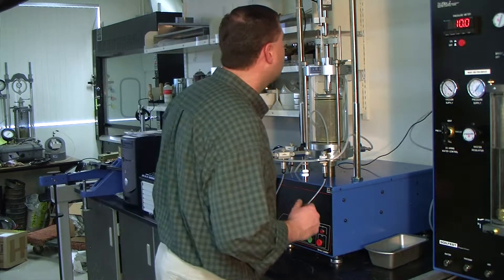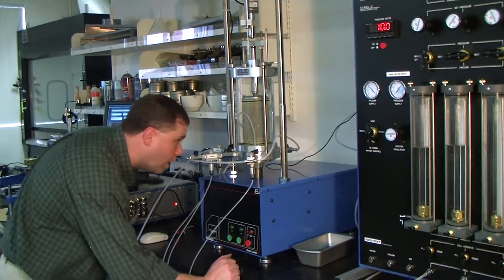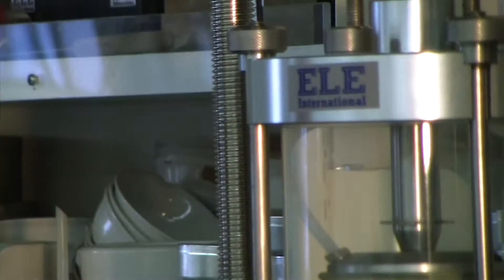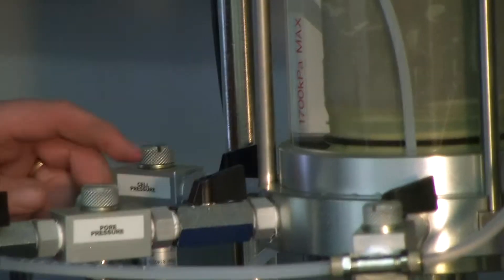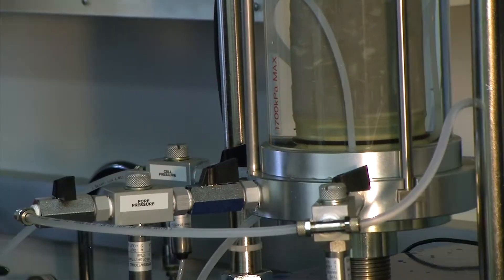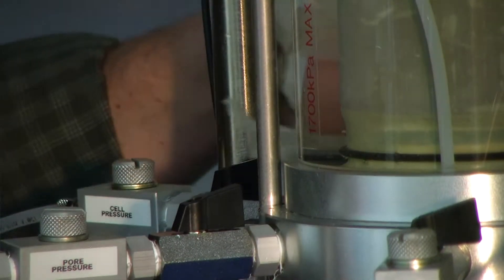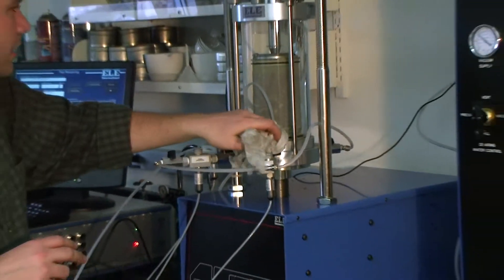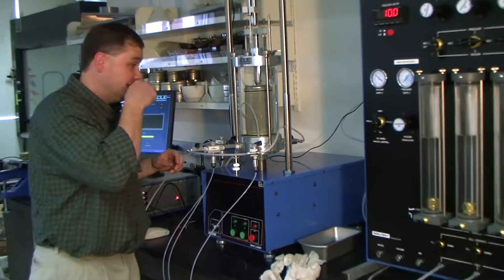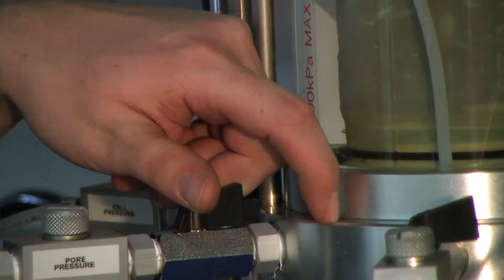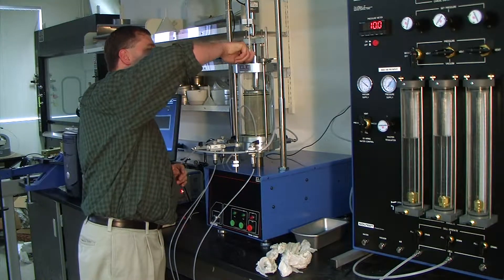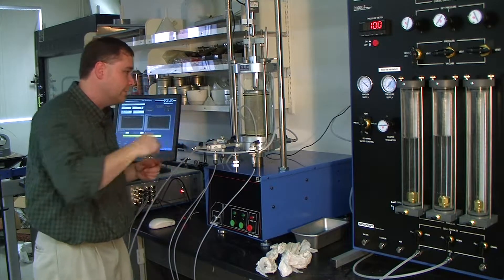What I want you to also do during every stage is to make sure you monitor if there are any water leaks throughout the entire system. There's a couple areas of water pooling around the bottom, but it's not continuously leaking. That was just some water that was on the O-ring area on the outside that's squeezed out because we've applied pressure. But watch those. I recommend you continue to monitor, clean them up and monitor them throughout the test, just to make sure that you're not leaking. If you are leaking from this location, typically that's due to some debris on that O-ring creating a path for the water to escape. You'll want to drain everything, start over again, remove that debris and clean up that O-ring. Check to make sure you're not leaking out of the bleed valve or any of the components you've assembled on the cell.